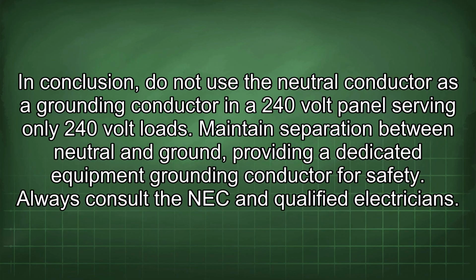In conclusion, do not use the neutral conductor as a grounding conductor in a 240-volt panel serving only 240-volt loads. Maintain separation between neutral and ground, providing a dedicated equipment grounding conductor for safety. Always consult the NEC and qualified electricians.